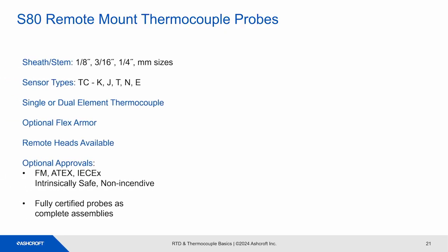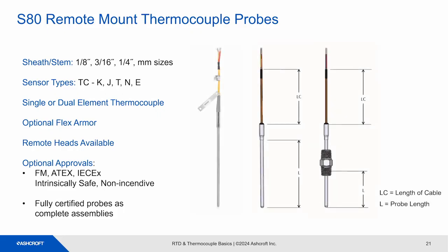S80 remote mount thermocouple probes. Common sheath diameters are 1/8, 3/16, and 1/4 inches, and 6 and 8 millimeter sizes. S80s offer K, J, T, N, and E thermocouple types. They are available with optional flex armor and remote heads. For approvals, we offer FM, ATEX, IECEx, intrinsically safe, and non-incendive approvals. The images show how the probe length and cable lengths are measured. If we install a spring-loaded fitting, like the image on the right, the L length is defined from the bottom of the threads to the tip of the probe.